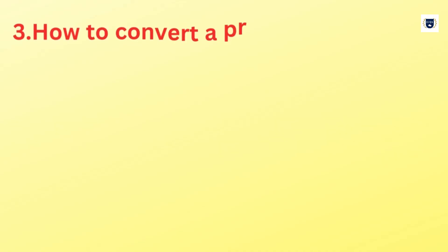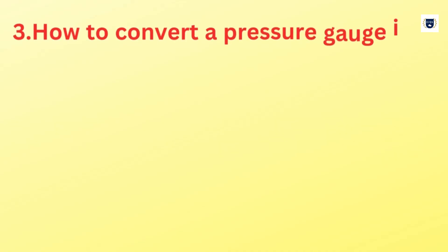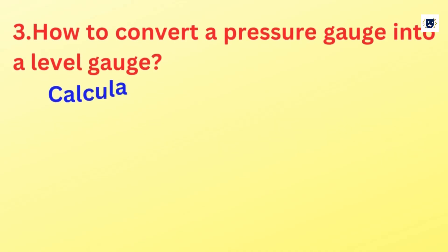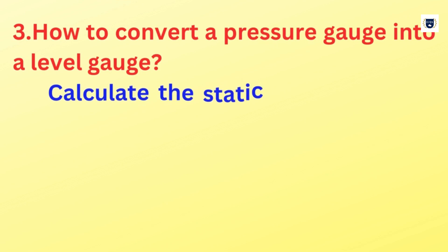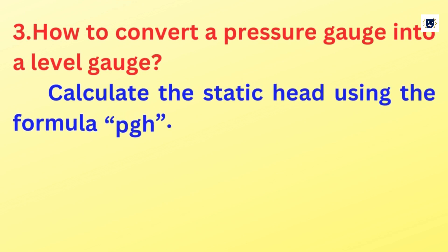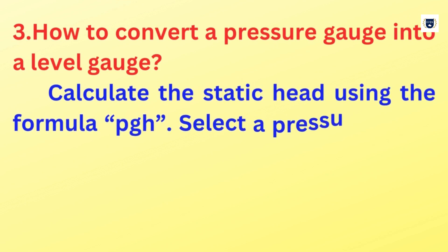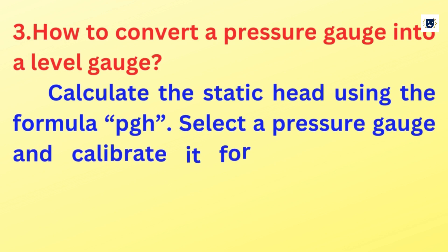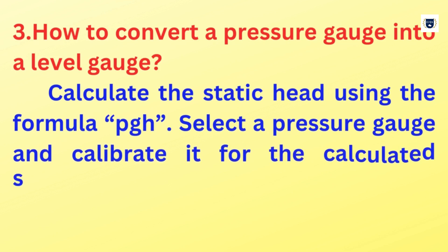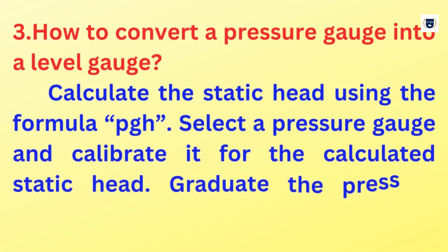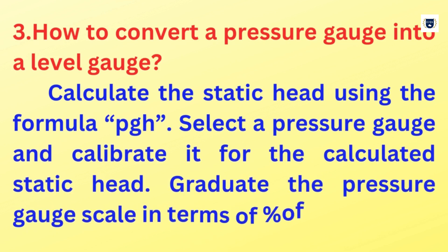How to convert a pressure gauge into a level gauge? Calculate the static head using the formula PGH. Select a pressure gauge and calibrate it for the calculated static head. Graduate the pressure gauge scale in terms of percent of level.